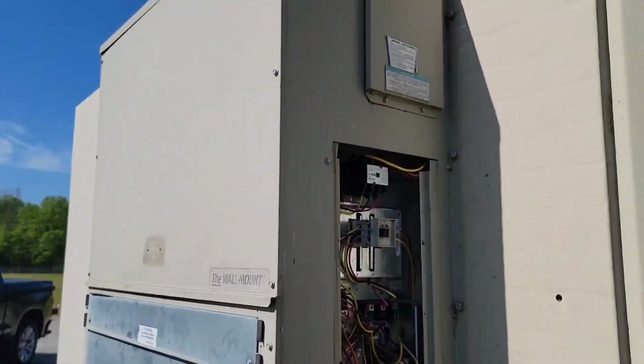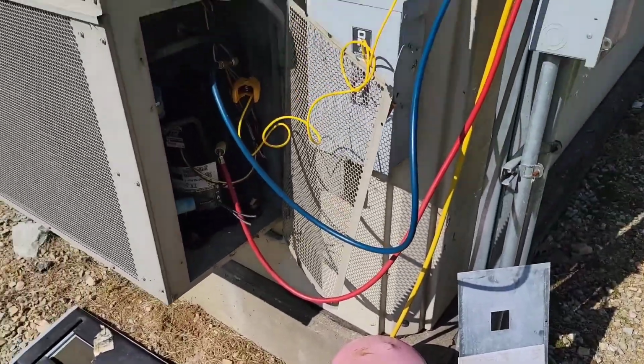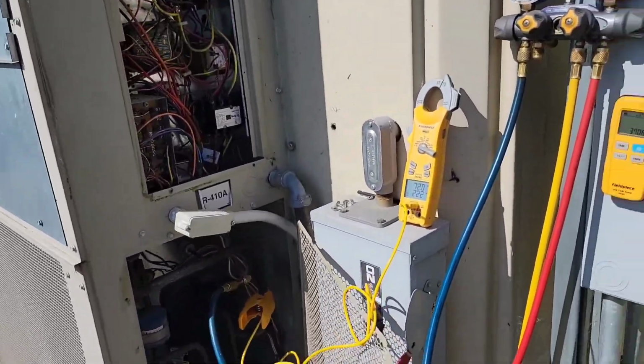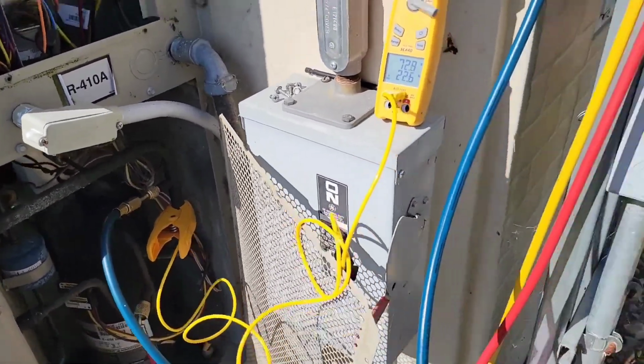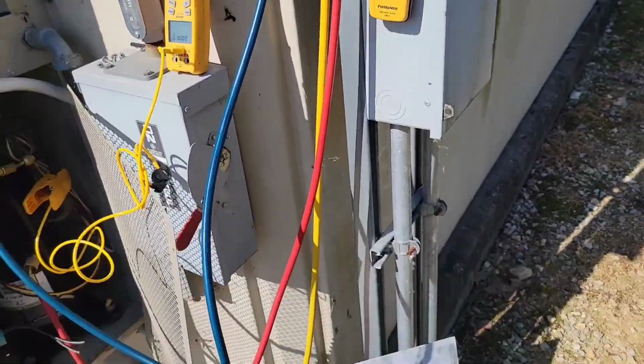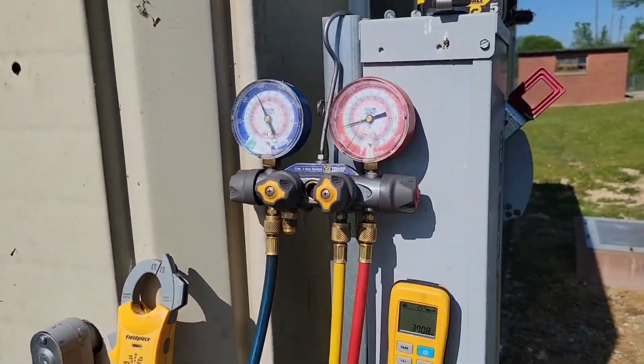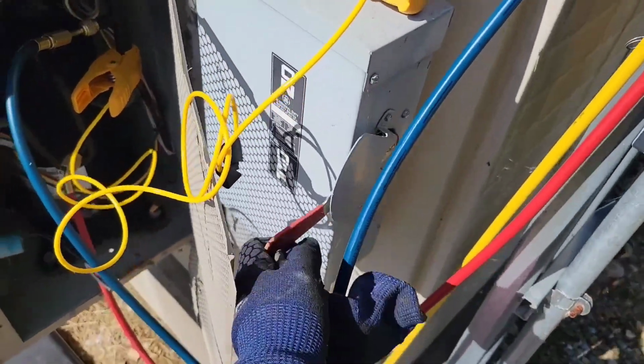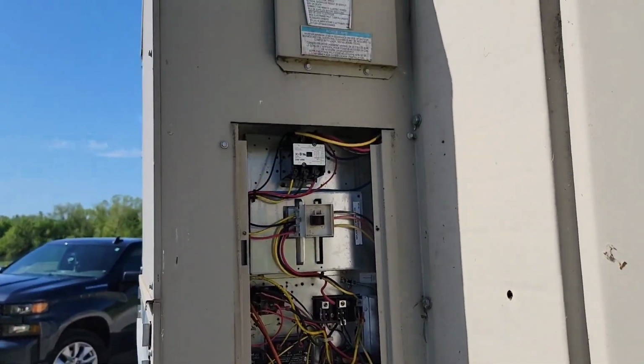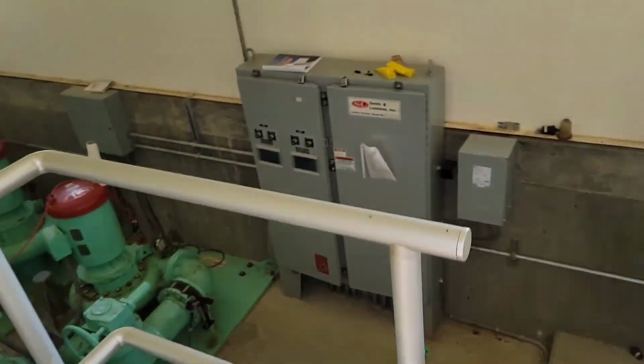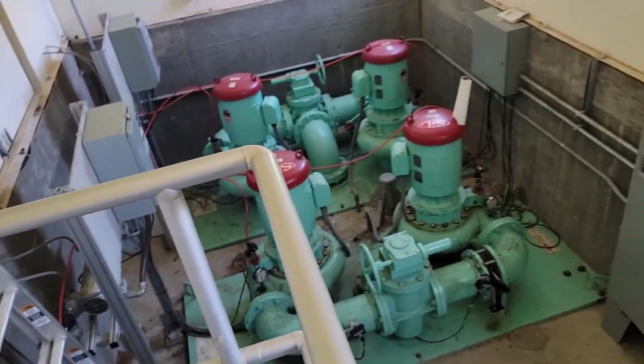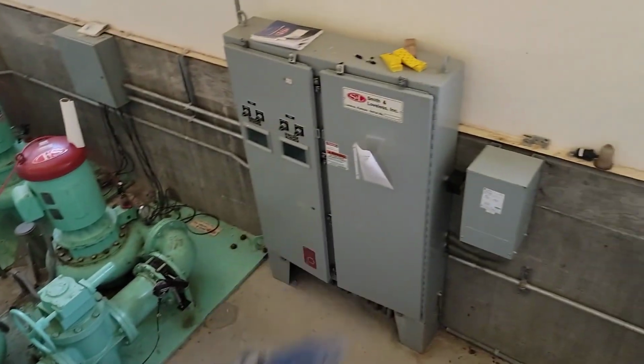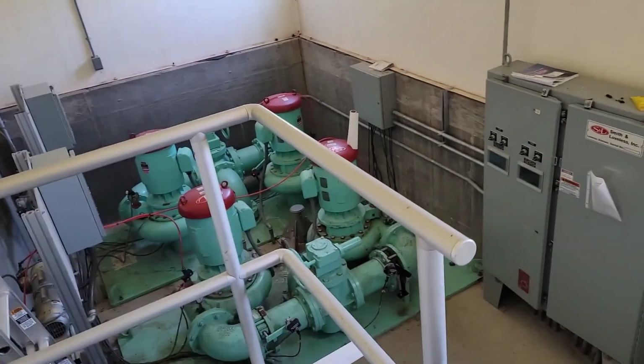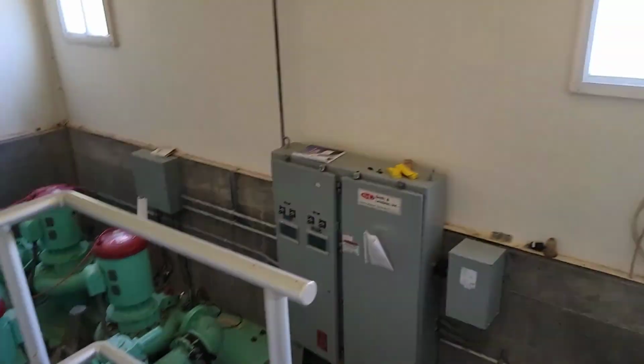Okay, so we got most of the panels back on. I have to charge this because they need this to cool the pumps inside, which I'll show you in a moment. So I got my clamp meter, I've got my scales, and I'm ready to put some more 410A in this system. So without further ado, let's get it kicked back on and start charging. Show you why we got to keep this little building cool. Our city's water depends on it. We got these pumps, we got these controls that drive the pumps, we got a transformer. So it's critical that we keep this building cool, especially when it's 85 degrees outside.